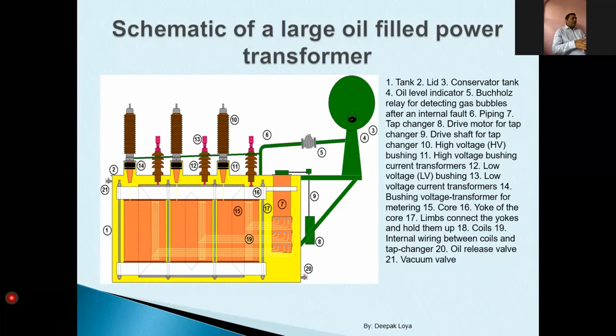Now, we have the oil level indicator, the fourth part, and it is there to know the oil level in my transformer. Because due to leakages or evaporation, if my oil quantity decreases, there will be an issue. My core coil assembly will not be cooled effectively. So I have to maintain a particular oil level in the transformer. I monitor this oil level in the conservator. If it comes below the lower level, we will fill it.